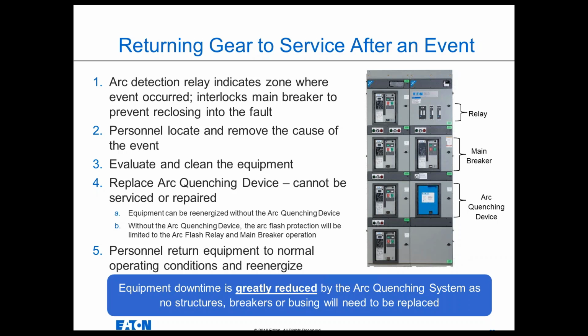So the equipment would be evaluated, it'd be returned to normal operating condition, and then the arc quenching device would be replaced. It's a one-time use device. We don't service them or repair them or refurbish them. They're removed, just drawn out of the switchgear, and a new one is put in service. Now, if a replacement device isn't available on the shelf, that's okay. The switchgear can still be re-energized with no device in the arc quenching device cell.